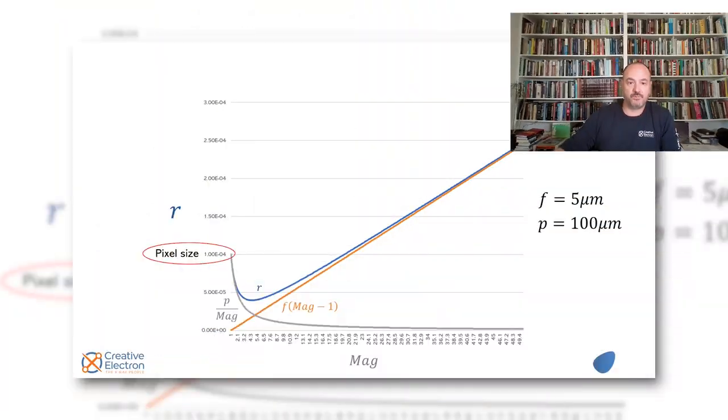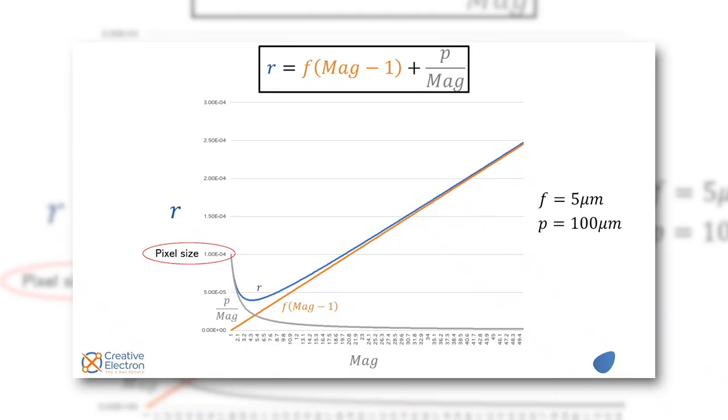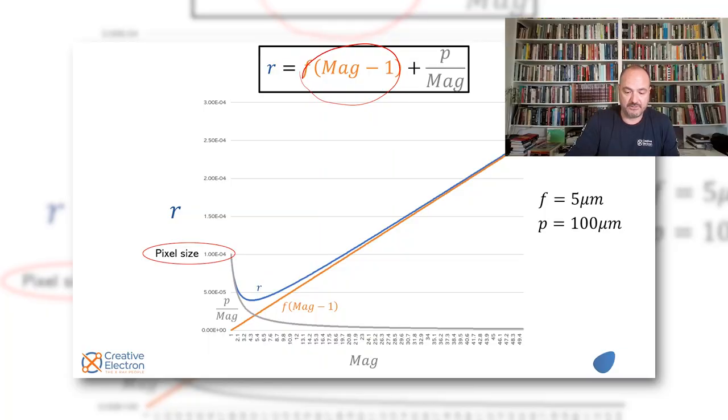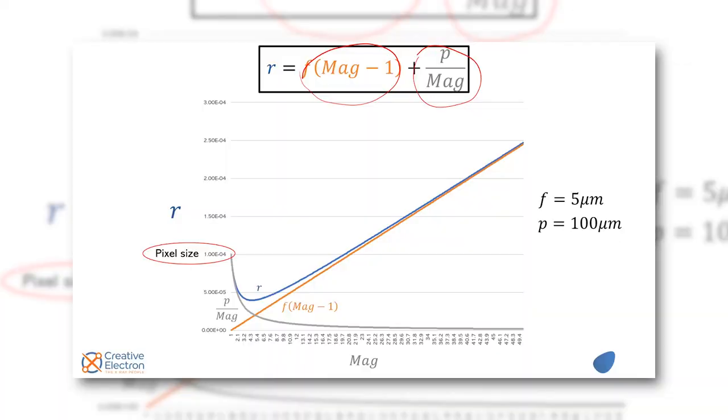So what we did here we were showing you three results at the same time. In orange you have an ideal detector where r equals f times mag minus one which is that straight line that we've seen before that represents a system where you have infinite pixels. On the other hand in silver we show you when you have an ideal x-ray source where resolution is driven by the size of the pixel and magnification. That's the inverse plot that we've seen before where the higher the magnification the better resolution, the smaller the number is.